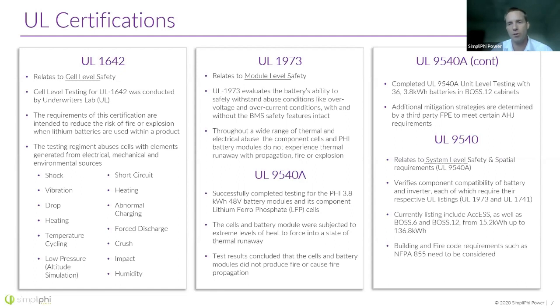That'll tell us what minimal spacing we can have between batteries, etc., when we go to do the UL 9540 certification, which is a system level certification. What I mean is if you have a battery backup system, an ESS system, that system will include an inverter, a charge controller, batteries, possibly batteries inside battery casings, etc. We take our systems through a system level certification, and anything matching that certification in the future will be able to be installed with 9540 certification.